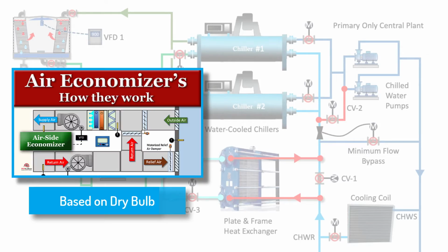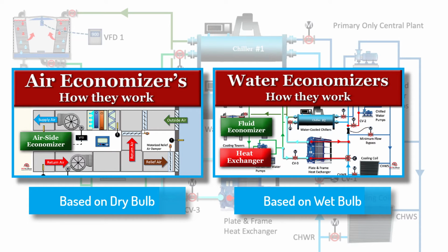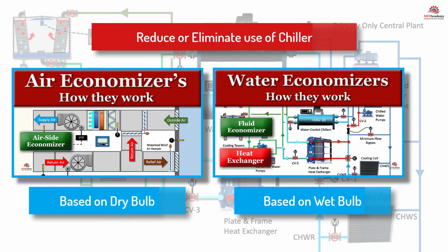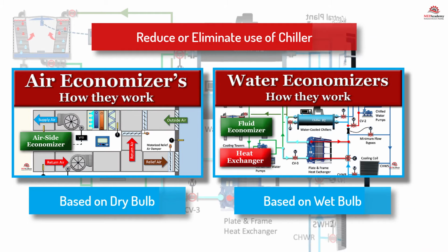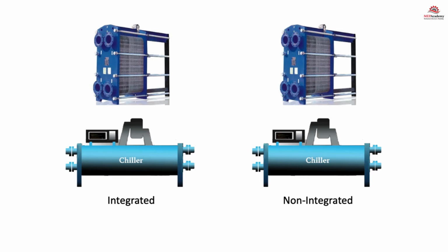In our previous video, we demonstrated how an airside economizer is based on the ambient dry bulb temperature, and now we'll show you that a waterside economizer is based on the ambient wet bulb temperature using evaporative cooling. The purpose of a waterside economizer is to reduce or eliminate the hours the mechanical cooling equipment must run, such as a chiller. Integrated versus non-integrated economizers.